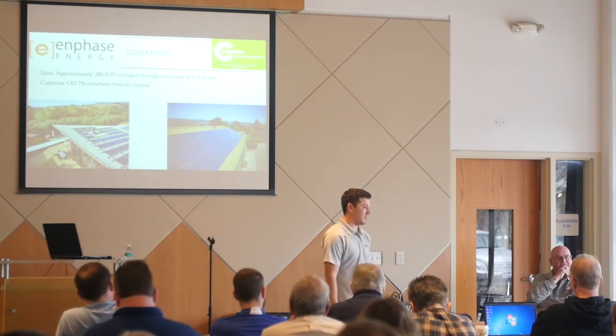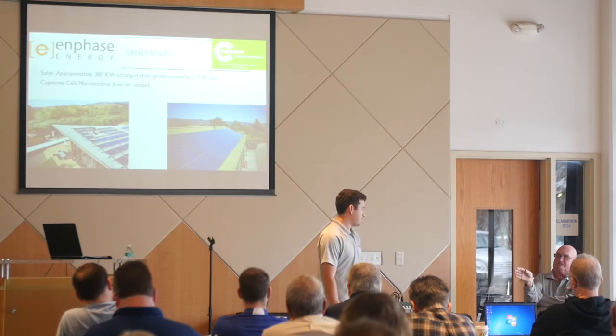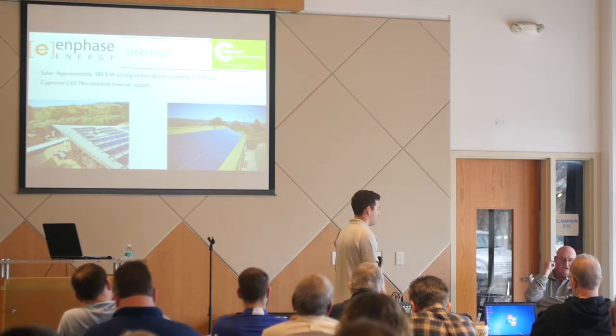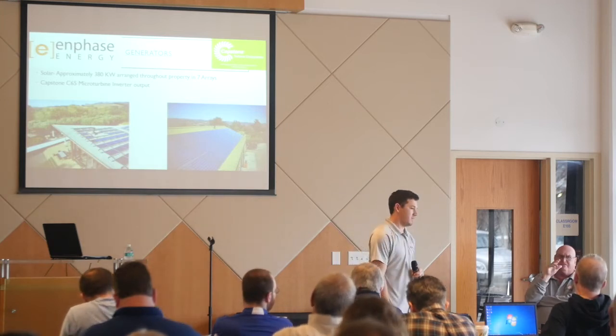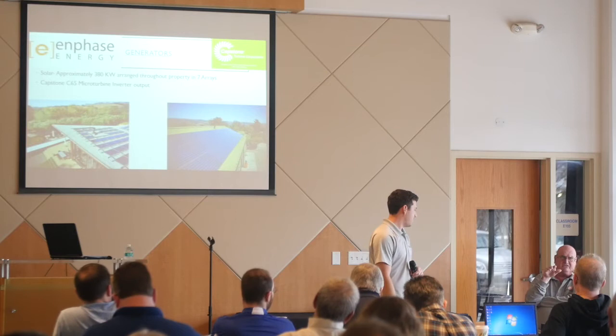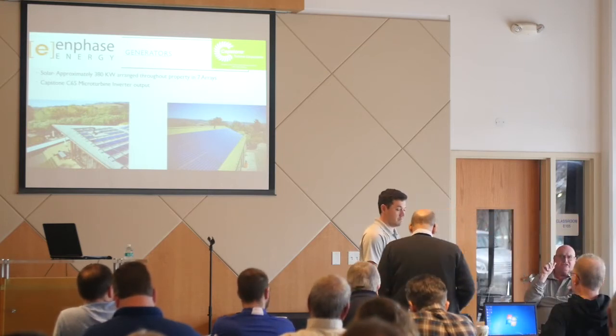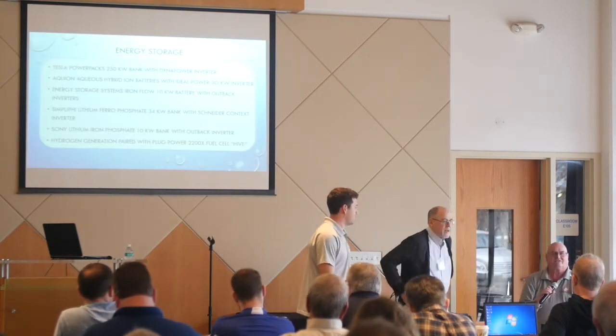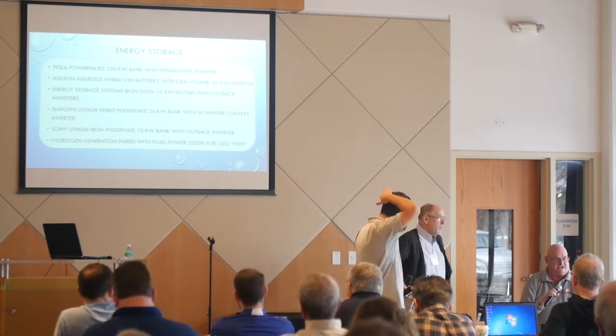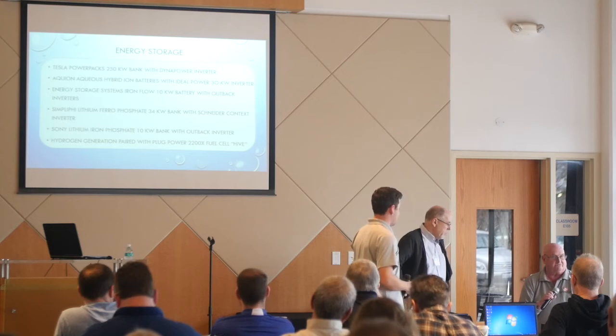Do you do any cooling of the inlet air for the turbine? We haven't yet, and I don't want to take the fire away from Ryan. One of the things I want to point out is we have 10 different kinds of inverters. We have no inertia in our system, no reciprocating mass. Even though the Capstone generator is a natural gas fired unit, it is in fact a DC generator. It's a jet engine in a box. A DC generator that has batteries on the bottom. It charges the batteries, and the batteries send the energy out through an inverter.